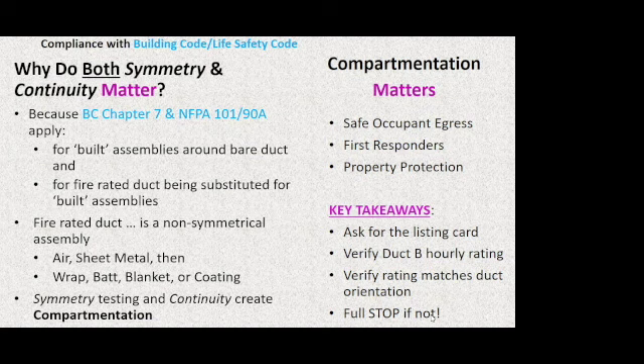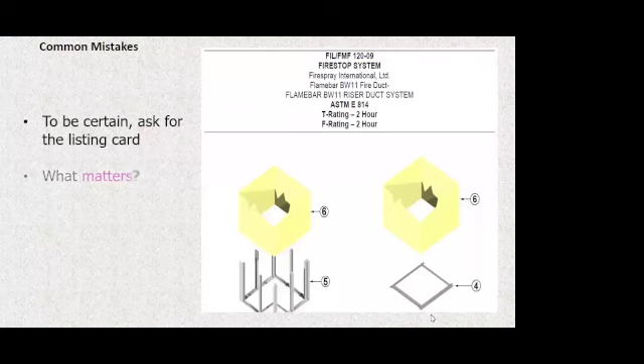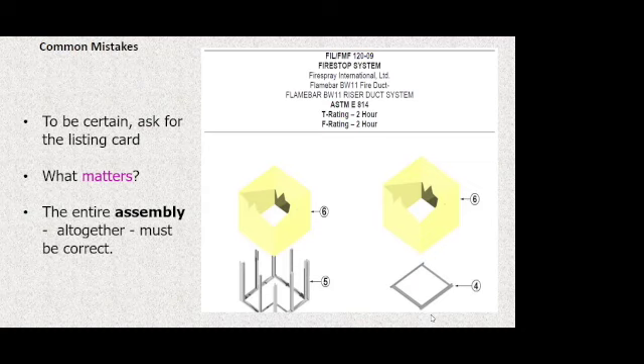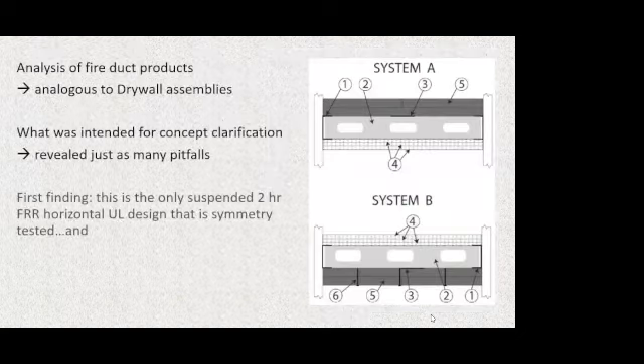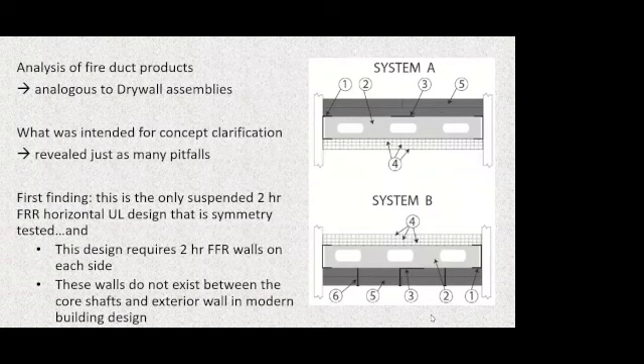Verify that it was actually tested in the orientation that you're seeing it, because yes, there are people who only test it in the vertical orientation and they don't test the horizontal orientation for the same configuration. That means that design cannot be used in the horizontal orientation because we know what? It's really hard to go horizontal and maintain the same hourly rating. If they skipped it, they're only allowed to use that configuration in the vertical orientation. And so there's all kinds of designs where it's been tested vertically and it changes once it goes horizontally. And once it goes horizontally, we need to switch to the horizontal configuration because the entire assembly is tested and it's allowed to be used in the orientation to which it was tested. We can't take vertical assemblies and use them horizontally any more than we can take assemblies that were only tested on one side and substitute them for built construction that was properly tested on both sides.